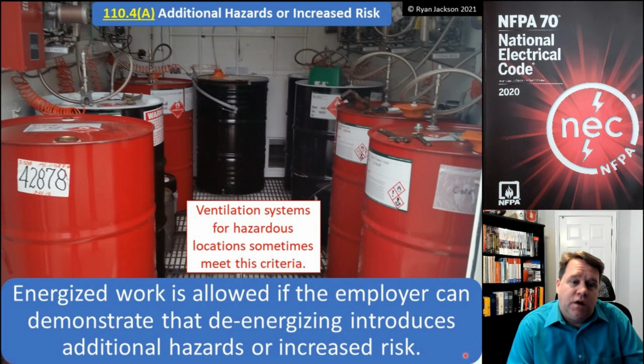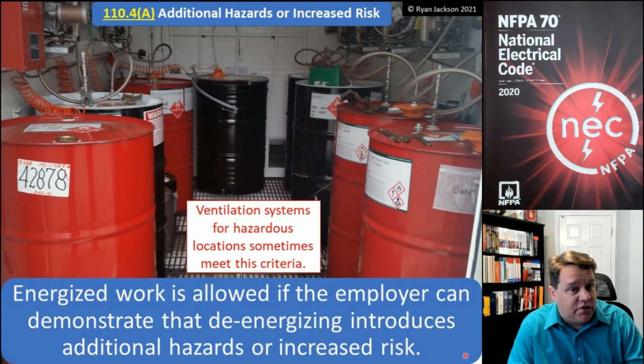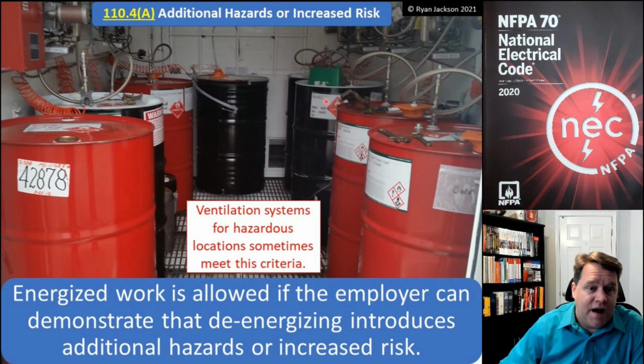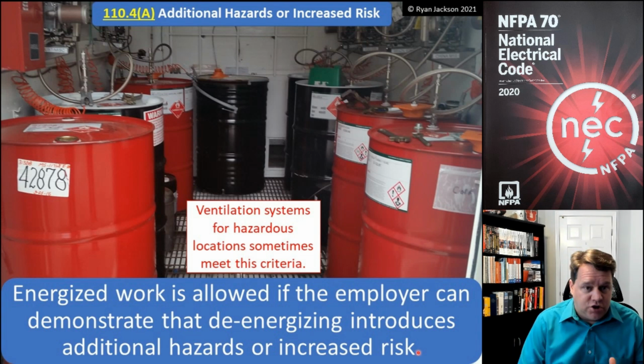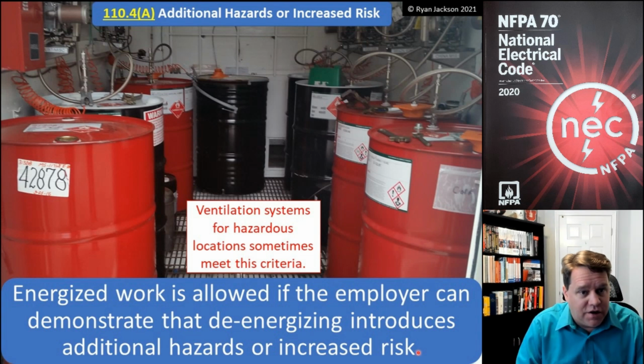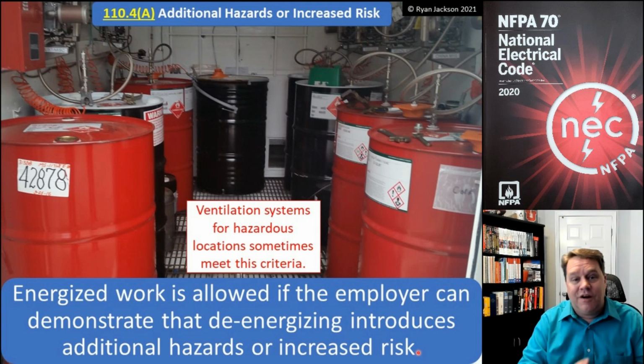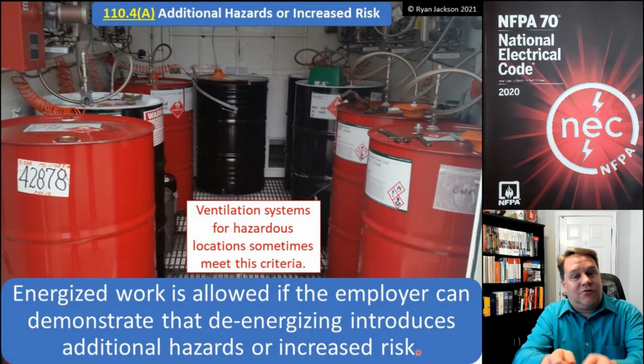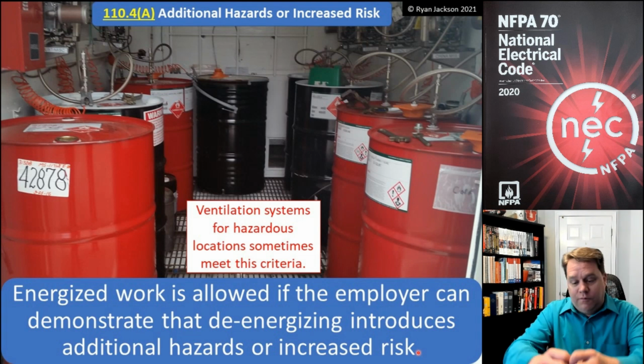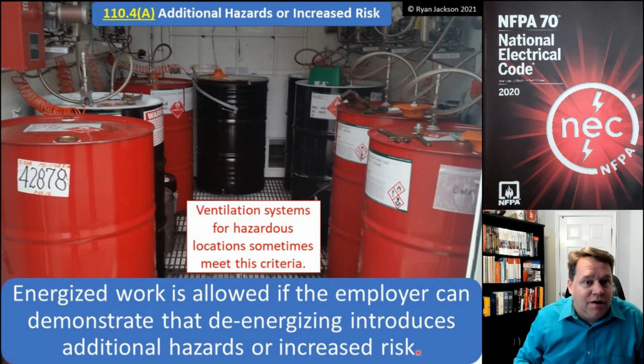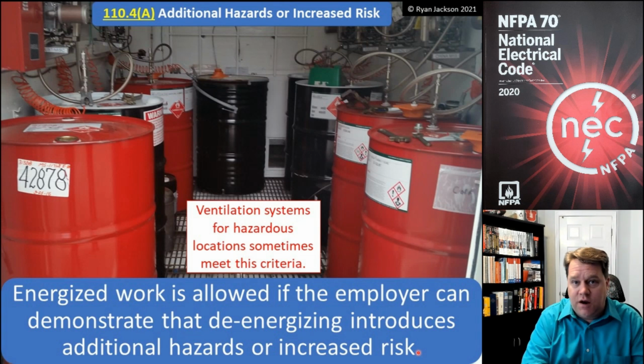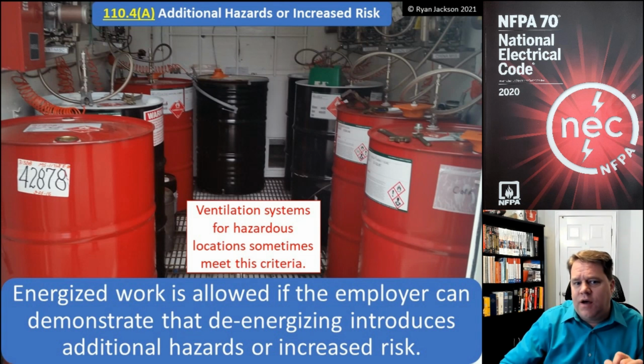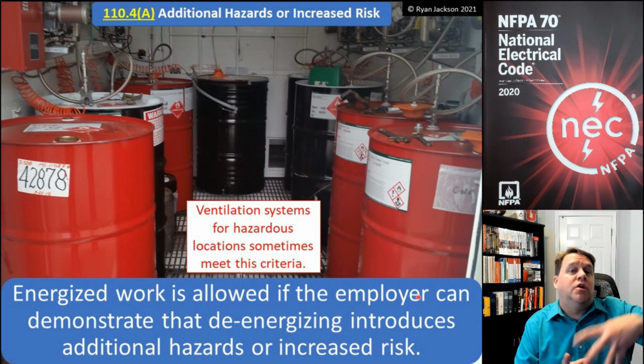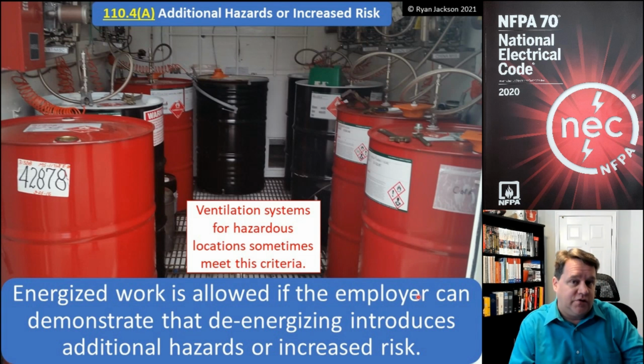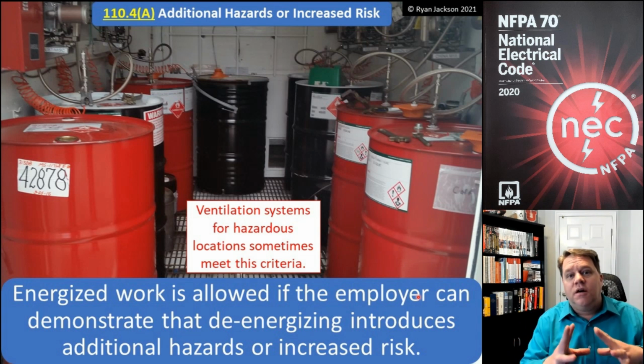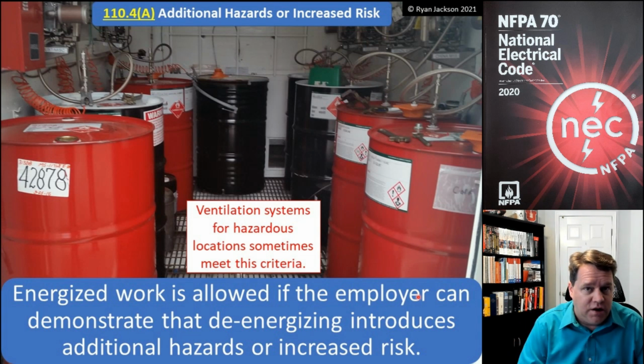All right, now what I'm showing here in the photograph is, of course, a hazardous location. We've got all of these containers of gasoline. You would never work energized in that building. Think about it for a minute. You've got all the gas vapors floating around in that room. Any sort of arc, spark, or bad thing would quite literally blow up the building. So you're not going to be working energized in here. So why am I showing a hazardous location? Well, because sometimes shutting off ventilation systems for a hazardous location could actually introduce additional hazards or increased risk.